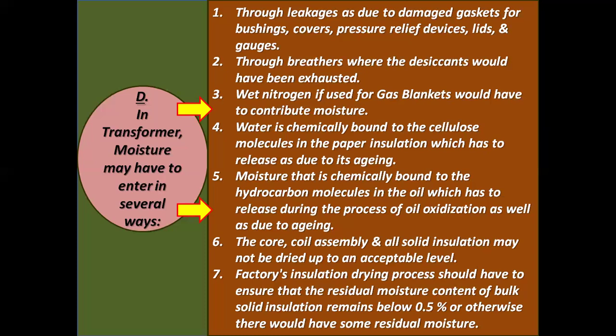The factory's insulation drying process should ensure that the residual moisture content of bulk solid insulation remains below 0.5%, or otherwise there would be some residual moisture. Again, I repeat, the factory's insulation drying process should ensure that the residual moisture content of bulk solid insulation remains below 0.5%, or otherwise there is some possibility of residual moisture.